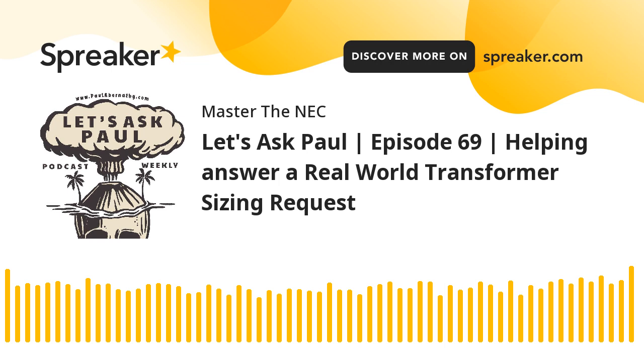So I'm just going to drop that 0.10. So I've got 36 amps of potential capacity for this transformer on the primary side, okay? All right, so one of the things that I look at now is, okay, now that I have this 36 amps, then I can go to 450.3(B) because now I want to protect this transformer.